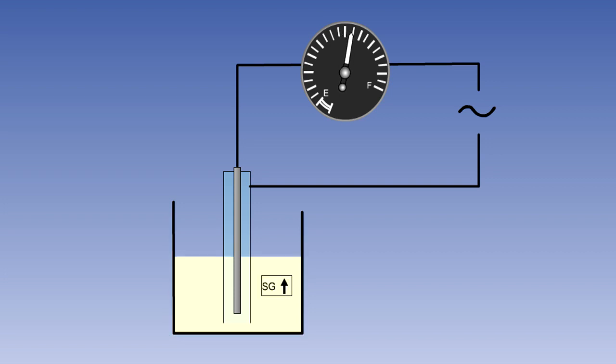The dielectric constant of fuel changes when its specific gravity changes. If the specific gravity of the fuel increases, more current will be allowed to flow in the circuit. And similarly, if the specific gravity decreases, the current flow will decrease.